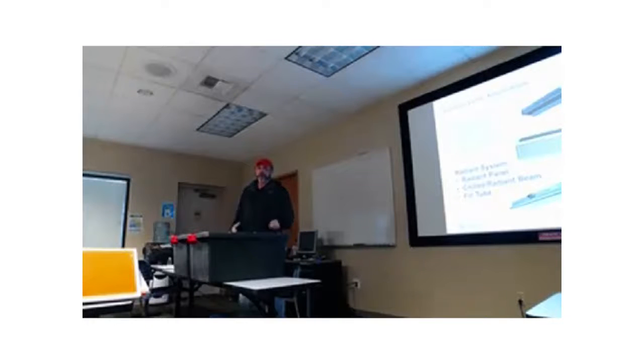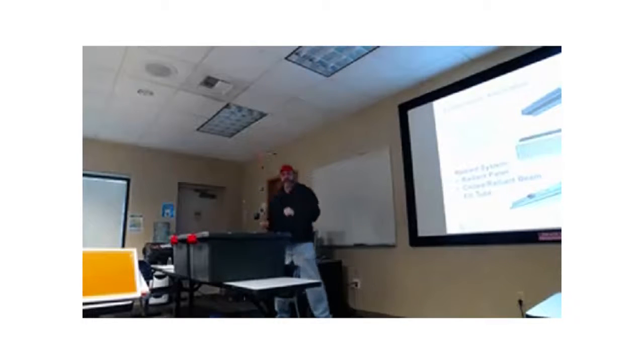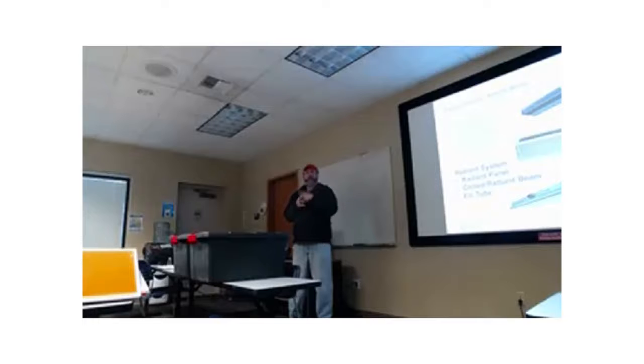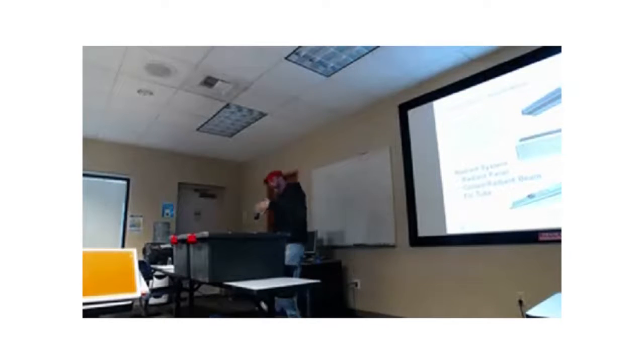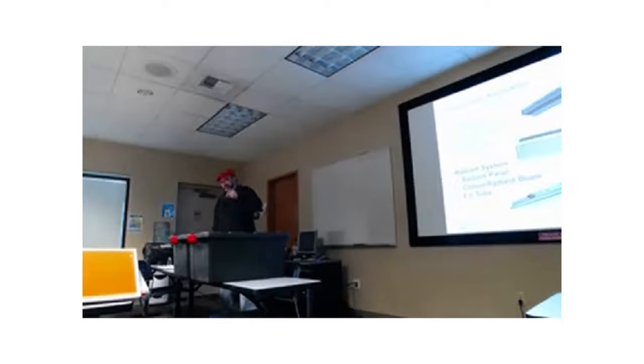some space, right? So what happens is, if you do the chilled beams, they don't need as much space above the ceiling, so you get smaller ductwork in. All you really need to do, if you design it right, is that the only air you need to provide to the space is the air for ventilation, right? So you can breathe, right?